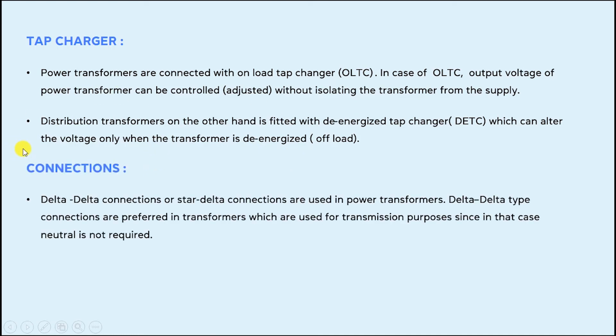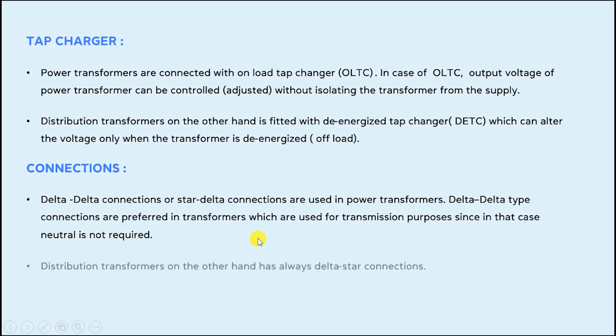The last point is the connections. Delta-delta or star-delta connections are used in power transformers. Delta-delta type connections are preferred in transformers used for transmission purposes since a neutral is not required during transmission. Distribution transformers, on the other hand, always use delta-star connections, which provide a neutral point.